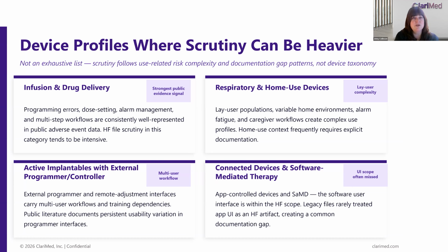So the product was launched and then apps or guides were added, and documentation wasn't necessarily put in place as it should have been from a human factors point of view. But it's true that apps that have hazard-related use scenarios or critical tasks or contain information for safety are fully within the scope of human factors engineering, and therefore the gap would need to be filled for any submissions.